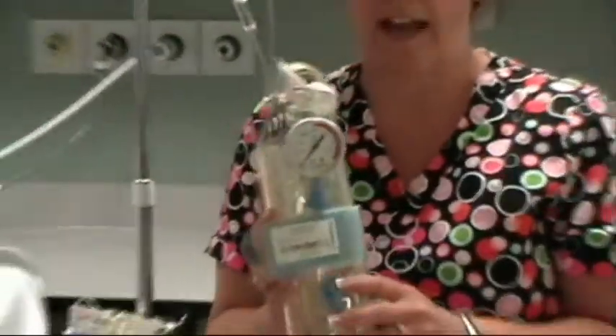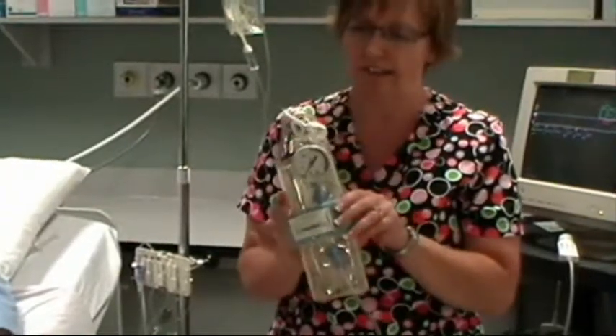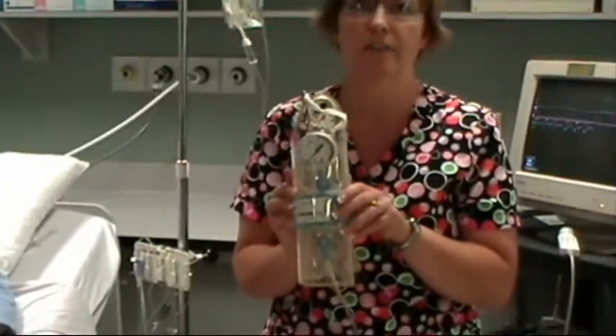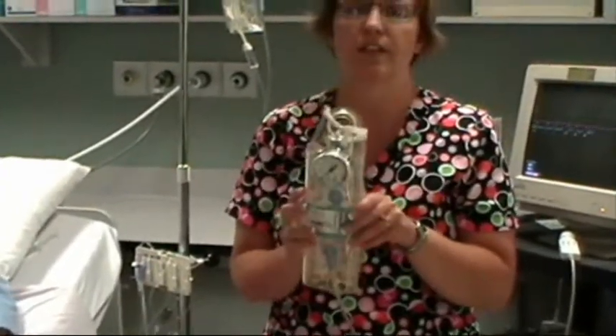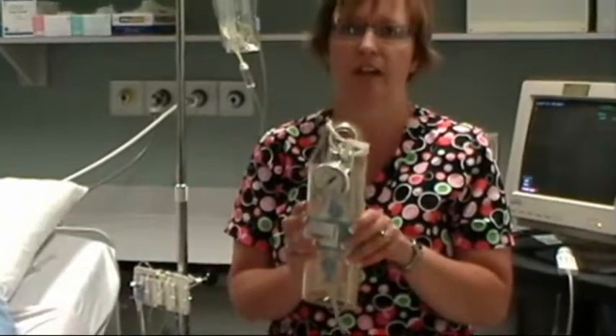And finally, you're going to add the pressure bag to the system. So you're going to inflate the pressure bag to 300 millimeters of mercury to ensure that you've got pressure on the system and you won't get backflow into the transducing system.